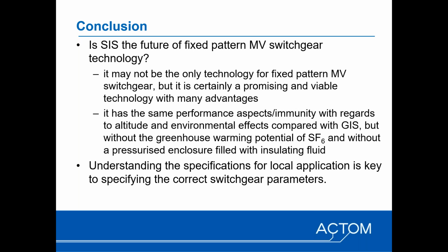And then in conclusion, is solid insulated switchgear the future? Well, it may not be the only technology available for fixed pattern MV switchgear, but it's certainly a promising and viable technology with many significant advantages, as I hope have become clear through this webinar. It has the same performance aspects or immunity with regards to altitude and environmental effects compared to GIS. GIS achieves this by virtue of the hermetically sealed and pressurized gas compartment, but solid insulation has the benefit of not having any global warming potential, GWP, as would be associated with SF6 and even some of the alternative gases, which, although they are much lower than SF6.